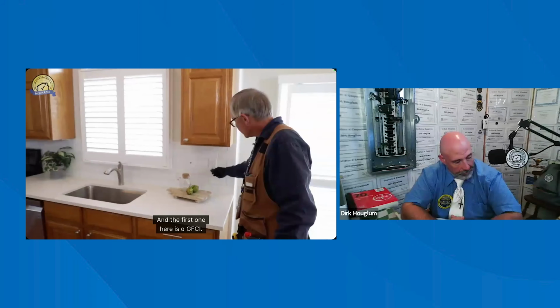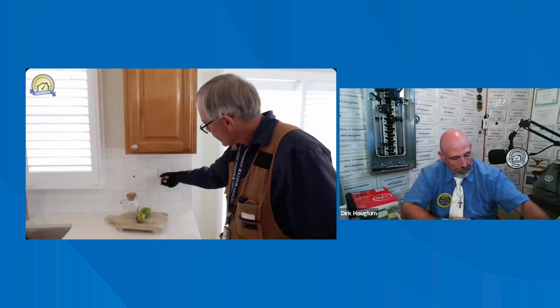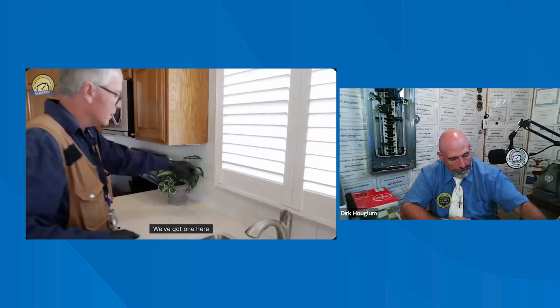Now we're in the kitchen, and we have all these receptacles up on the kitchen countertop, and I'm going to go ahead and test all of these. The first one here is a GFCI. I did the manual test with my tester, reset, and that one's okay. We've got one here very close to the sink, and according to today's code, we have to be within 6 feet. Anything within 6 feet from the outer edge of the kitchen sink has to be GFCI protected.